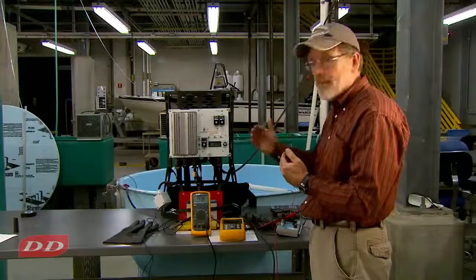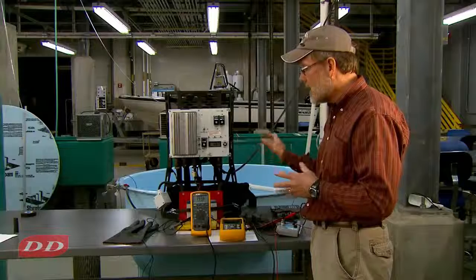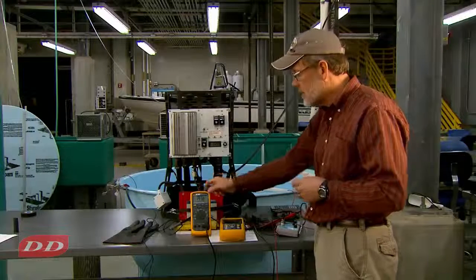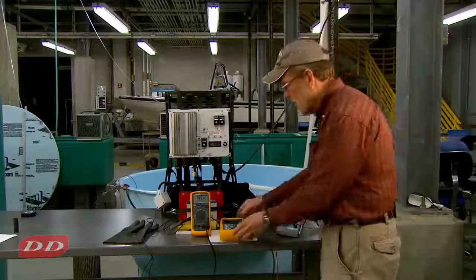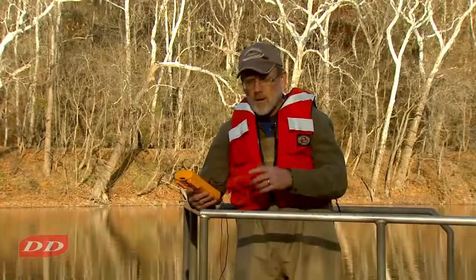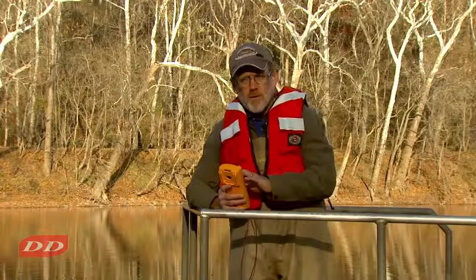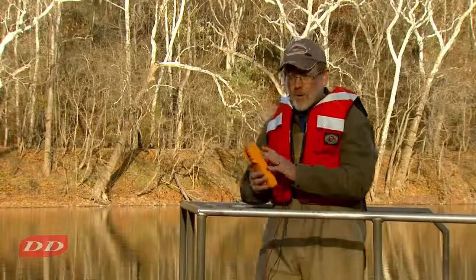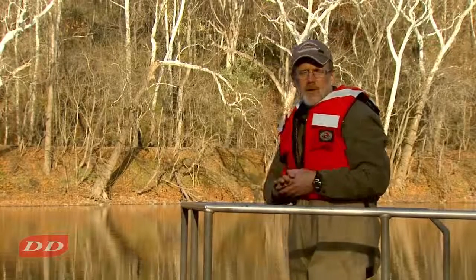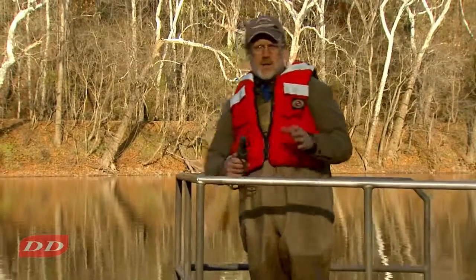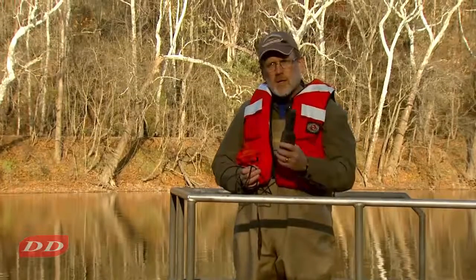You can go through various amp levels to see if the meter tracks the actual amps that are applied to electrodes by using a peak reading multimeter or a scope meter. So then you can run through the voltage measurements just like we did with the backpack unit, starting at low voltages and going up in increments and checking the voltage on the voltmeter and comparing that with what you're getting on your scope meter or on your multimeter. Then after that, you want to look at the current and look at the ammeter readings and check that. You don't want to break in line because you'll expose yourself to high voltage, so instead use a clamp-on ammeter.